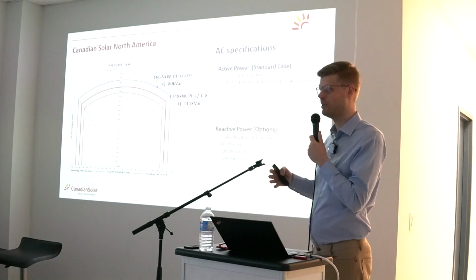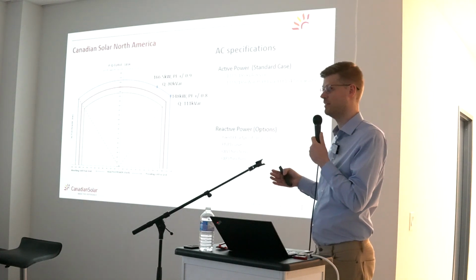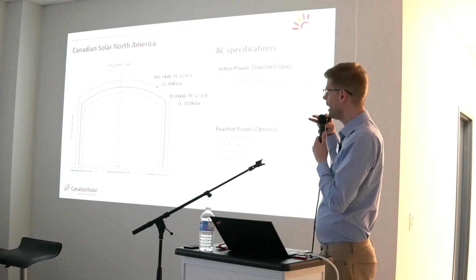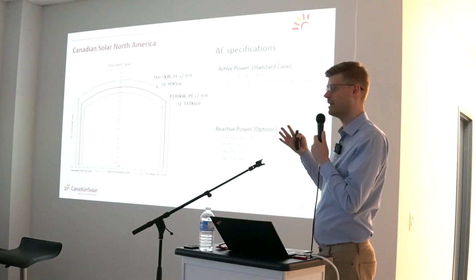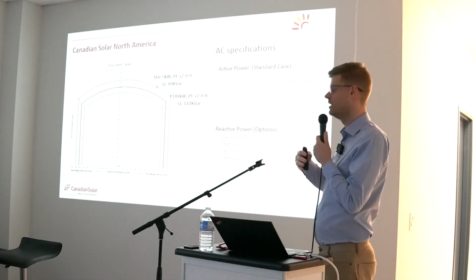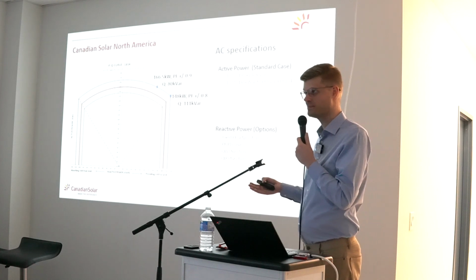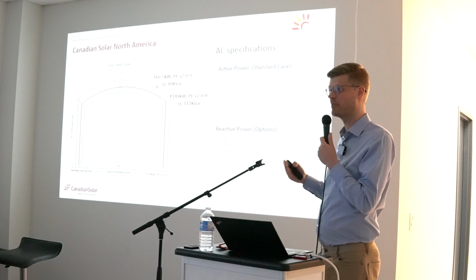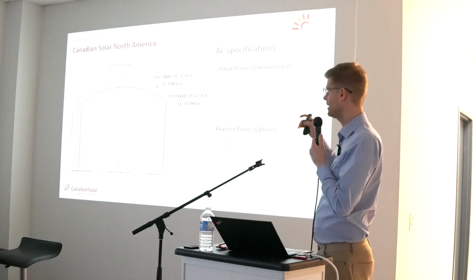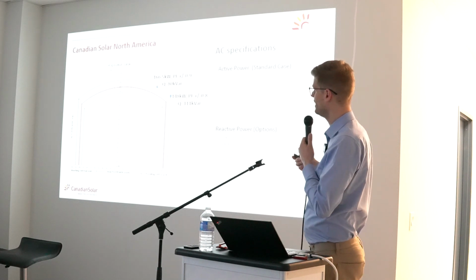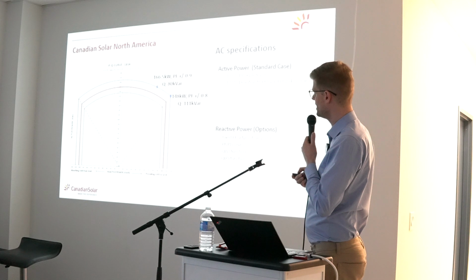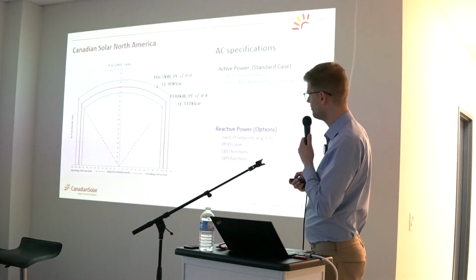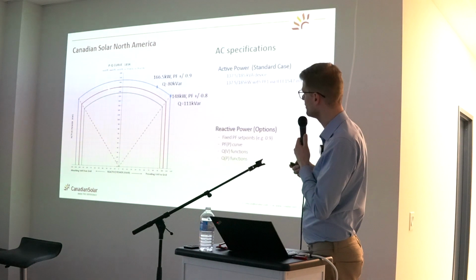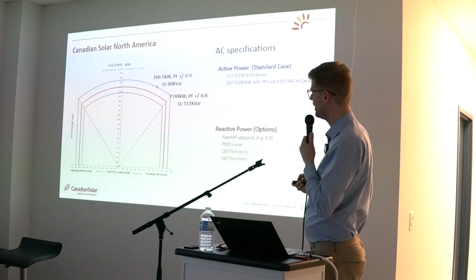and the apparent power is also 185 or 255. So there's no capacity additionally available for a reactive power component. So if the utility, for example, tells you you need to have a power factor of 0.9, the inverter will automatically lose active power capability because the apparent power stays at 250 kilowatts. So for example, here we have a PQ diagram of a 185, and we can see it here. We have the reactive power and the active power up here. If we have a power factor of 1, we will be operating here on that axis.